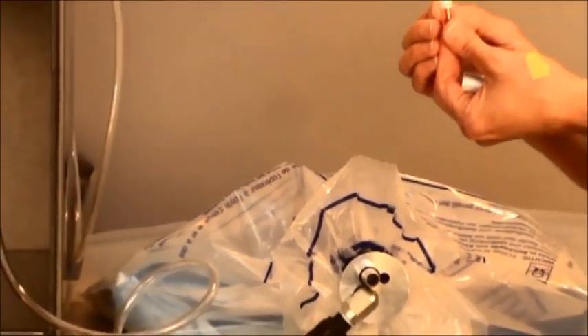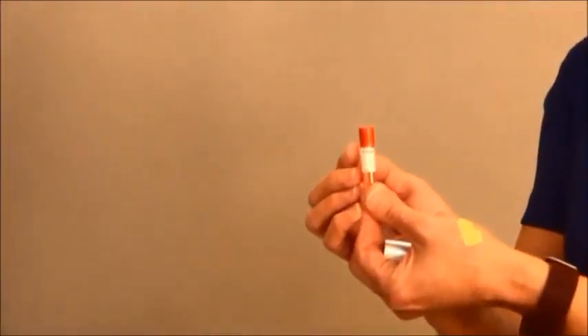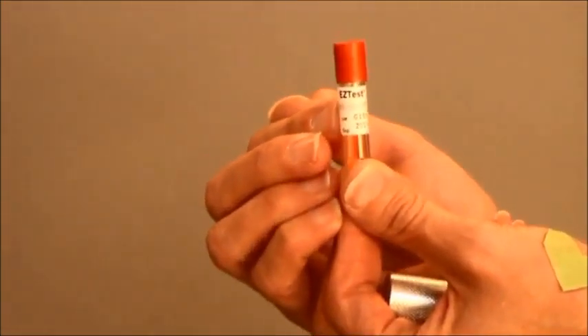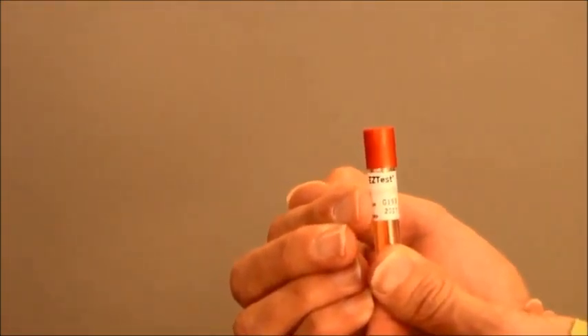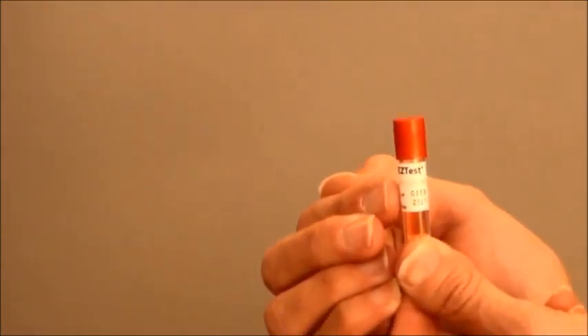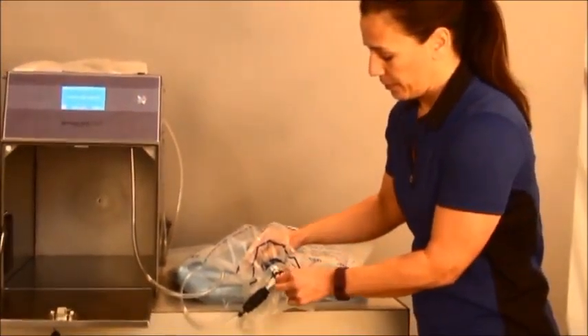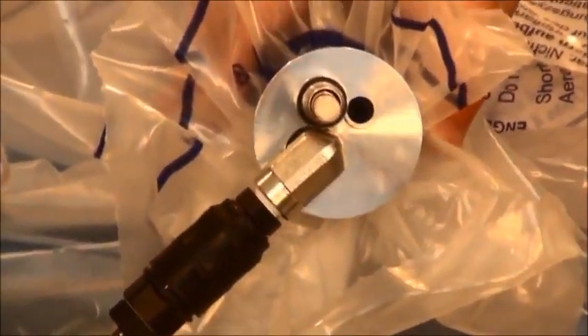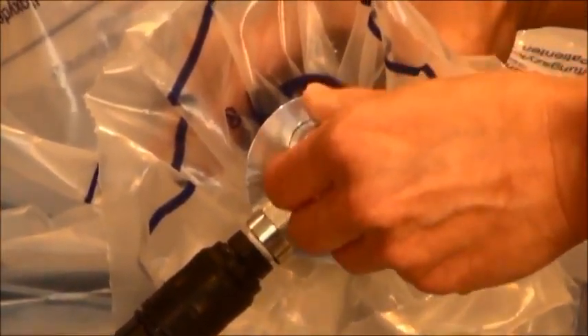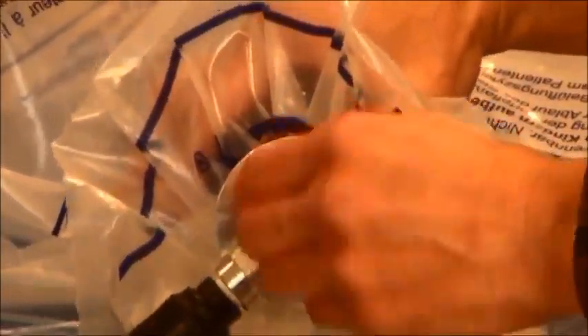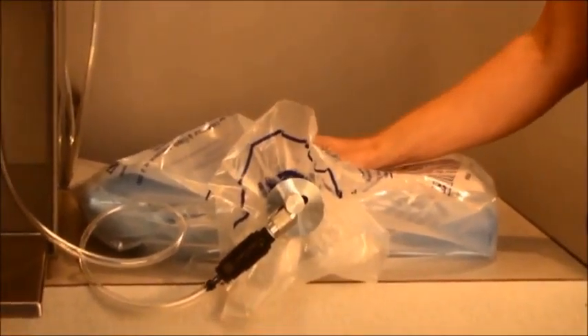The biological indicator has a red top. It also has an exposure strip here. The way you want to insert the biological indicator is cap down, placing it right into your PCD. Finally, you will put the cap back on your process challenge device, and your cycle is ready to start.